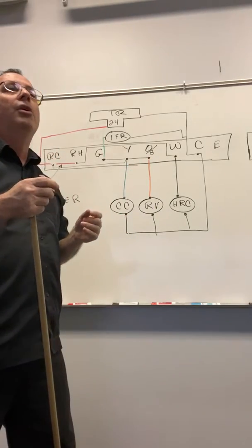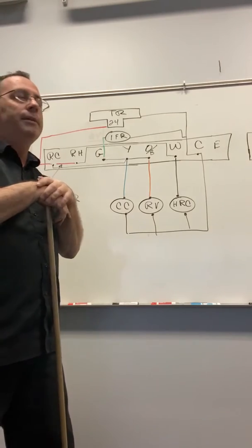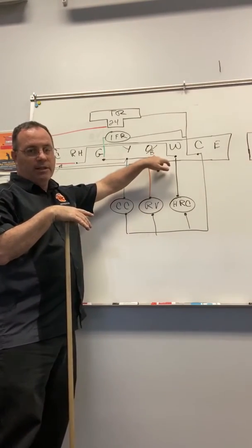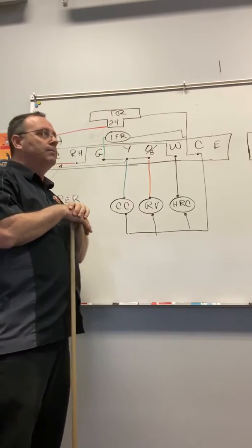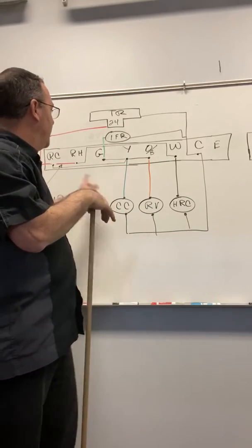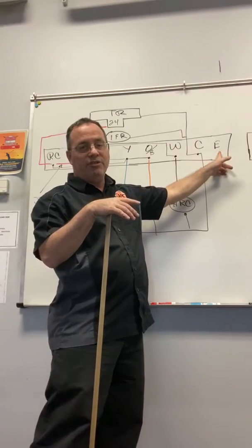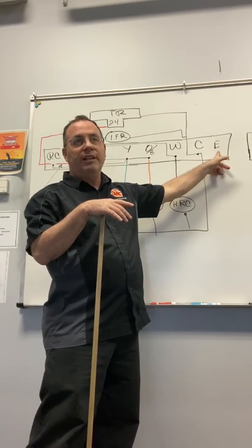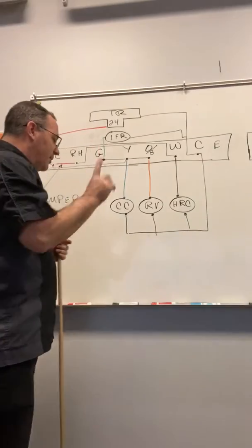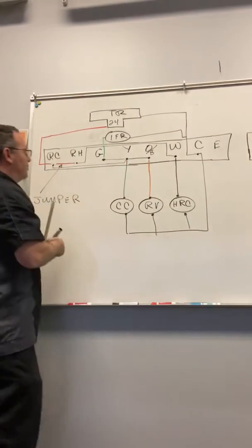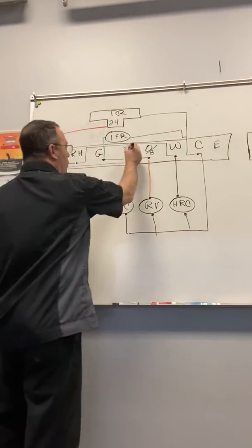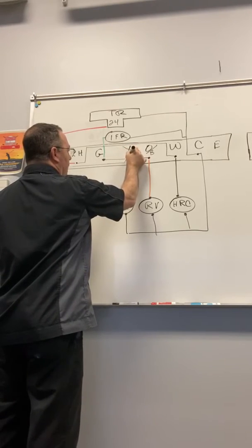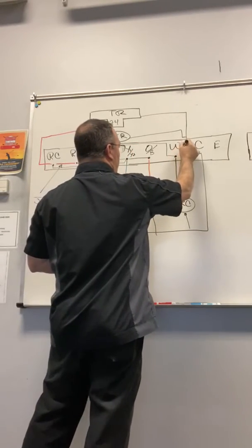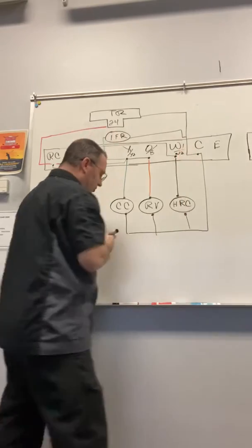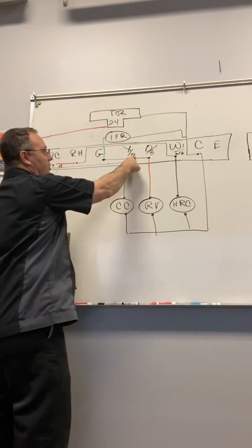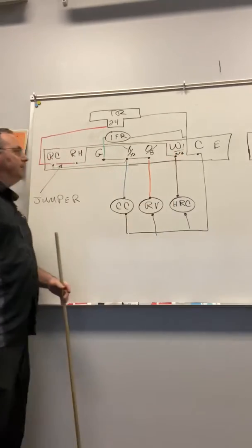Now I want you to recognize that the terminal B right here for O is a heat pump terminal. Some manufacturers use the letter B instead of O, so you have to pay a little attention to that. The other terminal you might run into is E for emergency heat. The only other ones you'll see sometimes are Y1 and Y2 and W1 and W2.